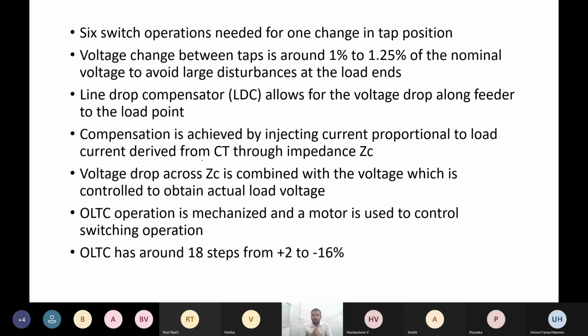So if you are applying the 400 volts, then the voltage difference between any two taps should be 1% to 1.25% of the 400. So 1% is nothing but your 4 volts. So 4 to 5 volts should be maintained between the two taps. Because of this, what happens is that it avoids any large disturbances at the load ends.